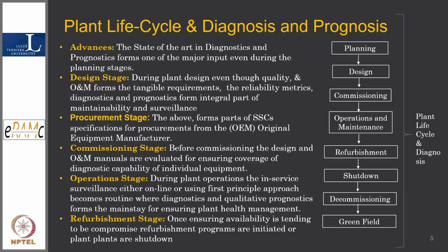The refurbishing stage is something very important. We want to track components which have operated for 40 years but will operate for 10 more, so we put additional sensors. It is very important in the refurbishment stage, whether it is a machine or a passive component like a pipeline or vessel, to monitor them online, because their margins have come down, and we should not go to a threatened stage where events can happen.